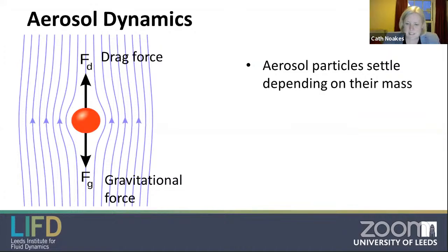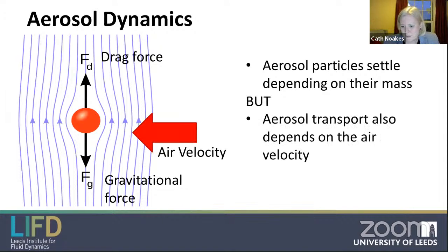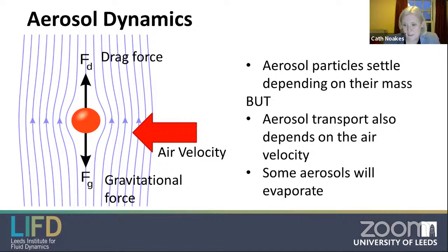A lot of the data that we can show on what happens to particles is dependent on the dynamics of the aerosol. So an awful lot of people will calculate how long does it take a particular size to settle. And that's based on the fact there's a particle settling in air, it has a drag force and a gravitational force. But we have to remember in real rooms, there's a velocity involved. And I've mentioned already the evaporation. So aerosol transport depends on what happens to the air in a room. So we can't just say, oh, settling time in still air gives us X.